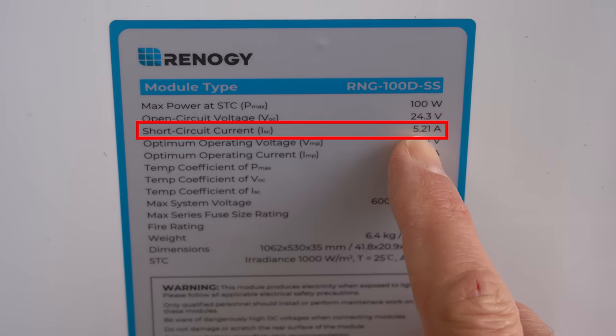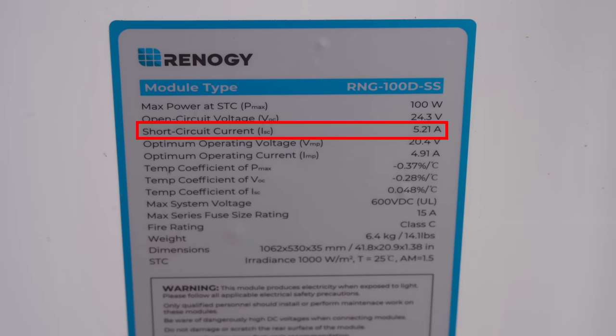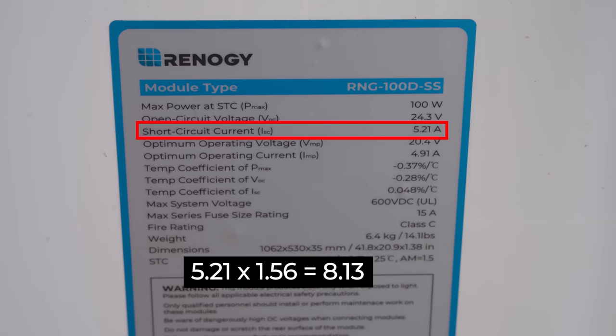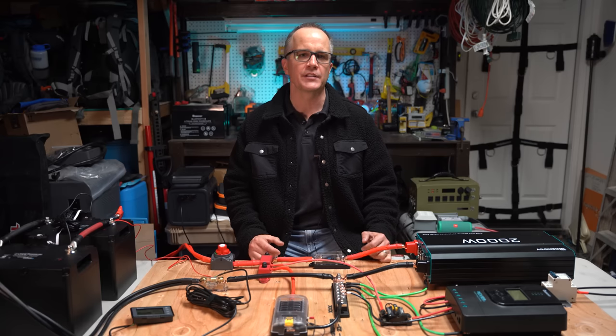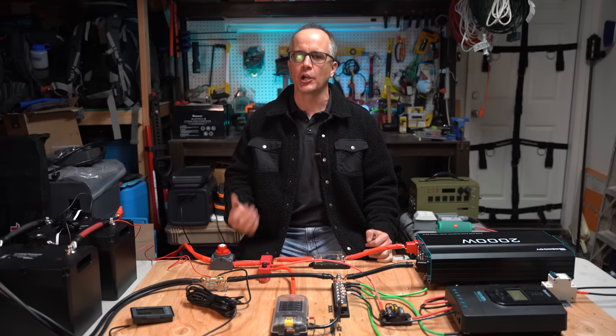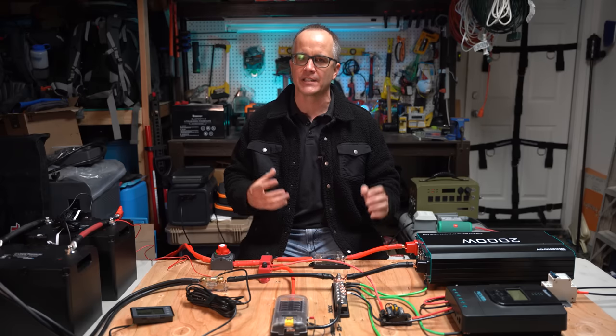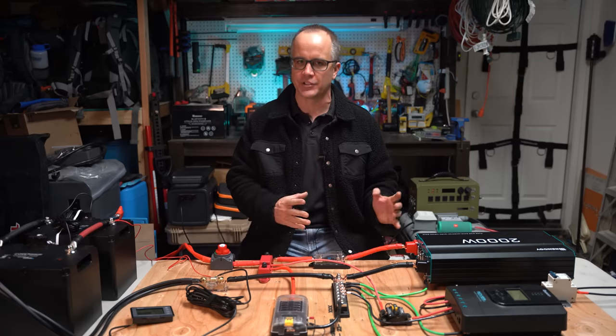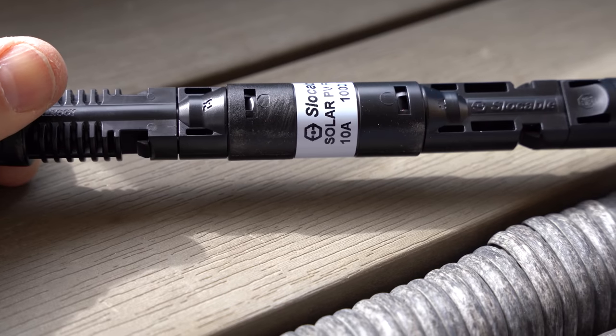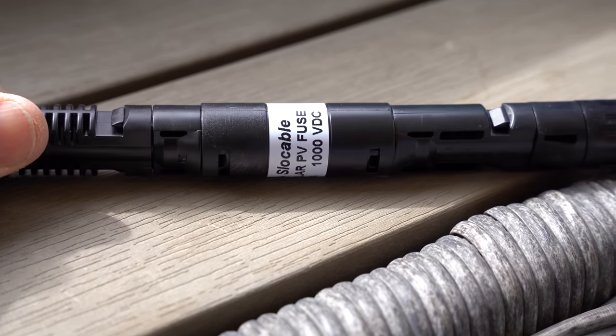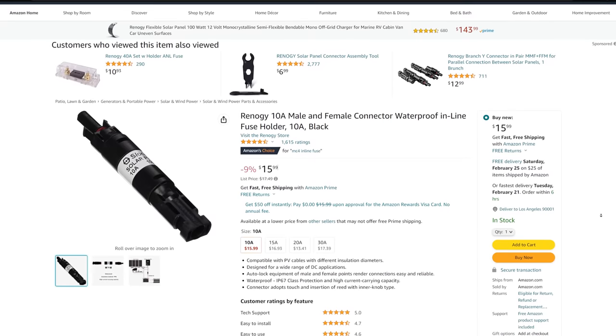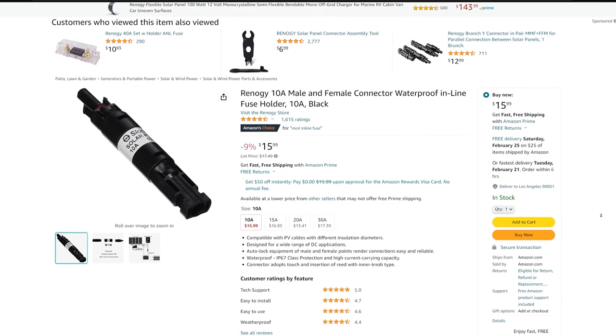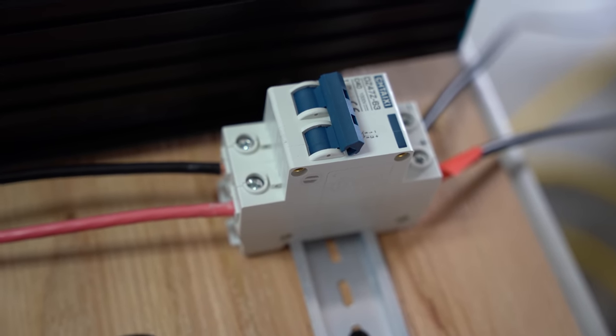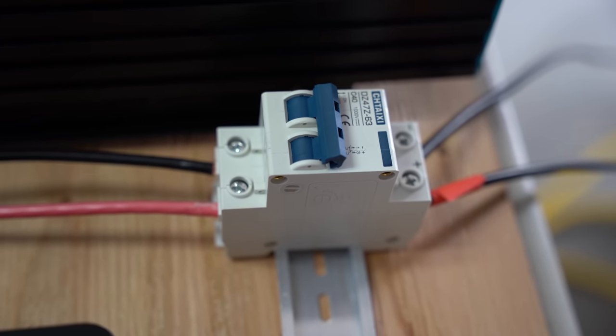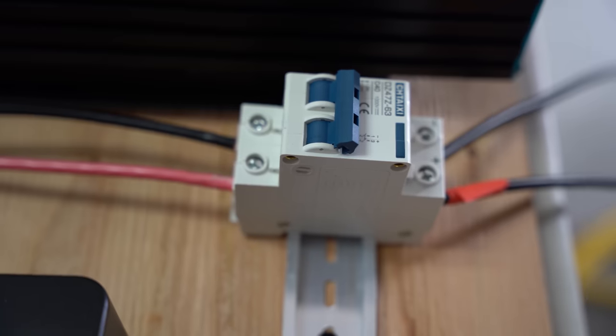So, to determine the fuse size to put on the positive wire coming from the solar panels connected in series, I multiply 5.21 by a factor of 1.56, which gives us 8.13. Now, getting into a lengthy discussion of where we get 1.56 is again beyond the scope of this video, but it's a value that in this industry is standard to determine the fuse size to connect to the solar panels. Again, with our calculated value of 8.13, we need to find a fuse this size or larger. Looking online, I found an inline MC4 fuse, which is rated for 10 amps, shown here. Now, before we connect our solar panels to our charge controller, I want to install a disconnect switch that allows us to easily disconnect our solar from our system.